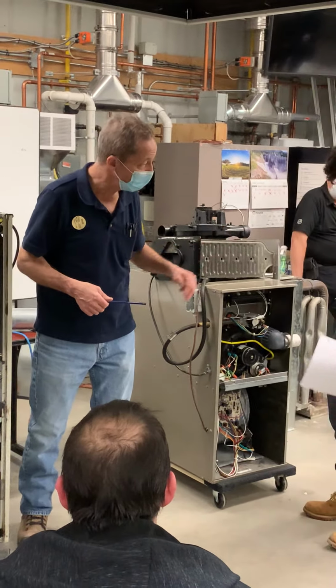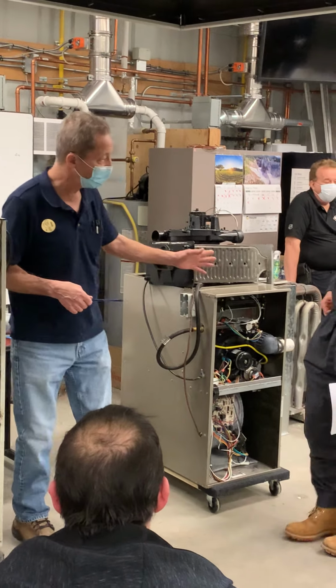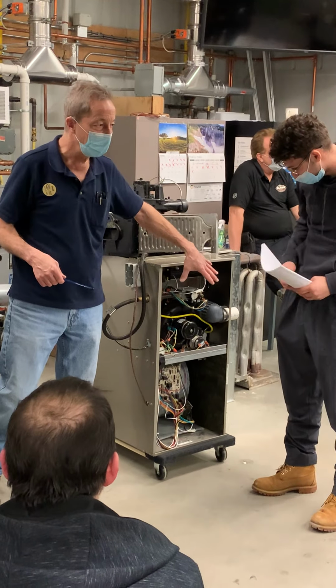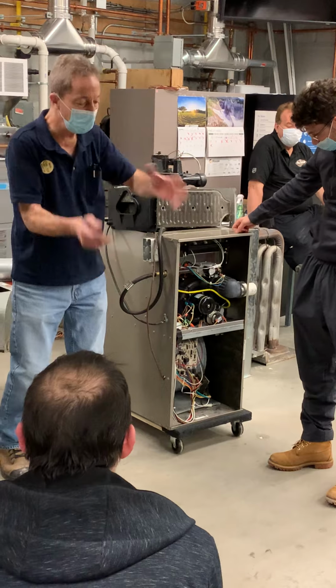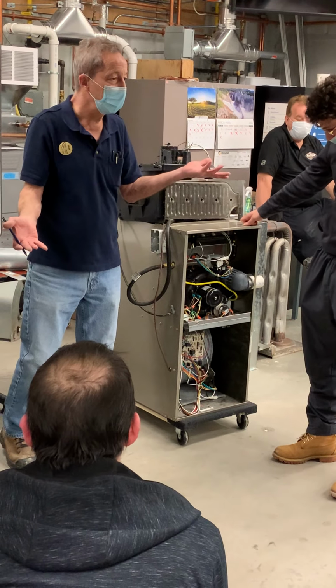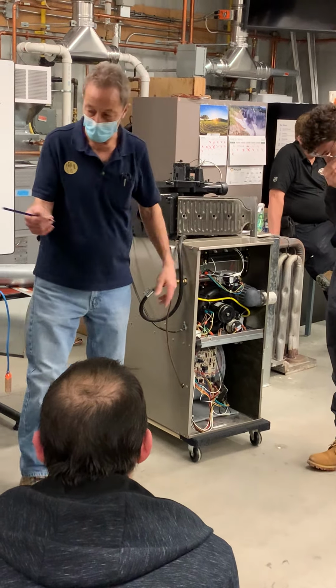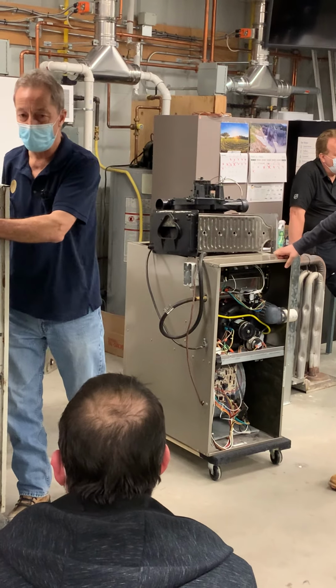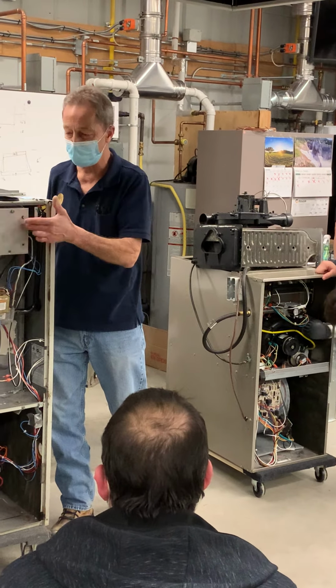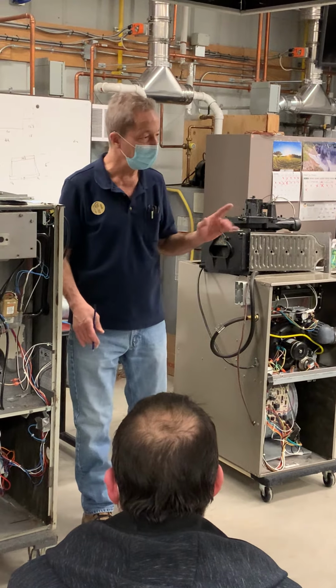Did you say two? Yeah. Okay, so this one has two because it's a more open burner assembly. If I rotate left, right, up, down, I want it to trip. This one only needs one because it's a sealed burner box. If there's a flame rollout in here, this is going to pick up on it. Okay, so we're clear on that.